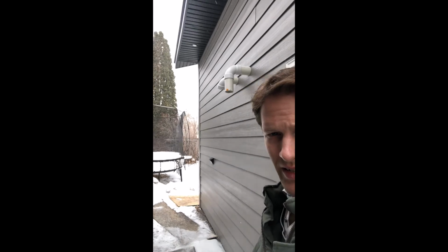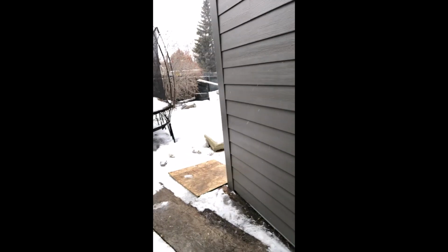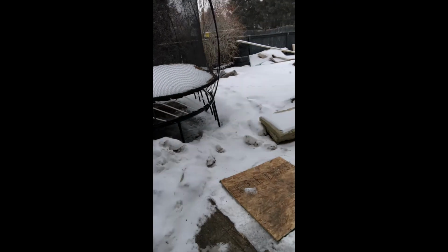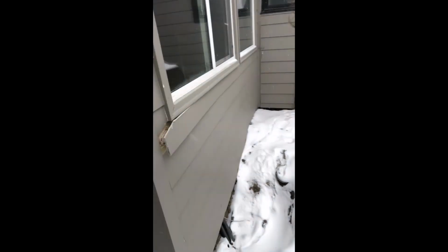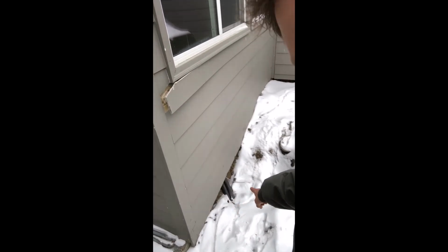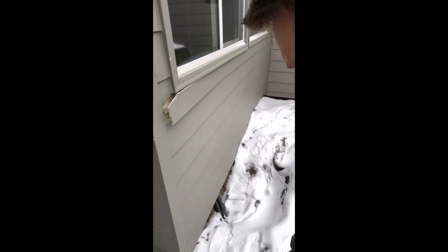Ugh, it's snowing again. Okay, so on the outside here we got our exhaust and intake for the boiler, and under all this mess we've got insulated PEX piping running up into the sunroom, and you can kind of see the 2 insulated PEX lines going up into the sunroom there. I drilled a hole through the concrete and made that work back in the summer.